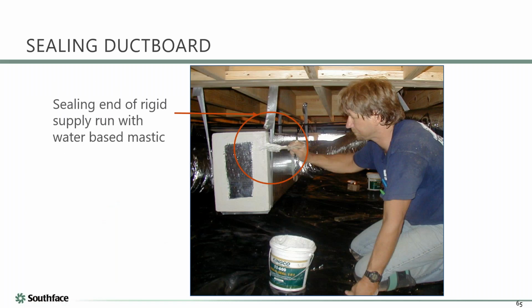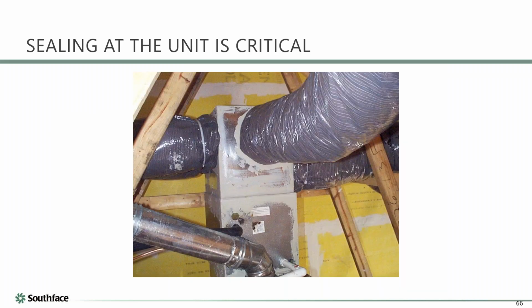And of course, with ductboard, we want to do the outside. Georgia says if you want to assemble ductboard with silver tape, that's fine, but you're going to have to cover it with mastic to seal it. How thick? Thick as a nickel, about 2 millimeters thick. So the edge of a nickel is the thickness you want. And then of course, where is the pressure the highest in a duct system?